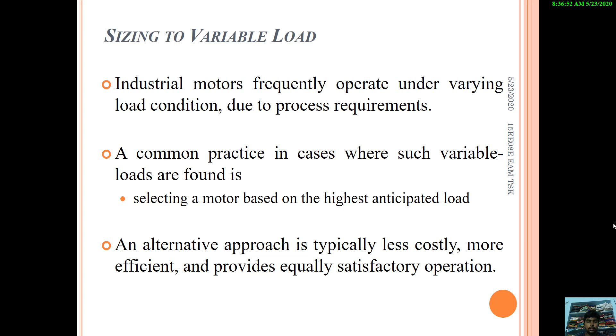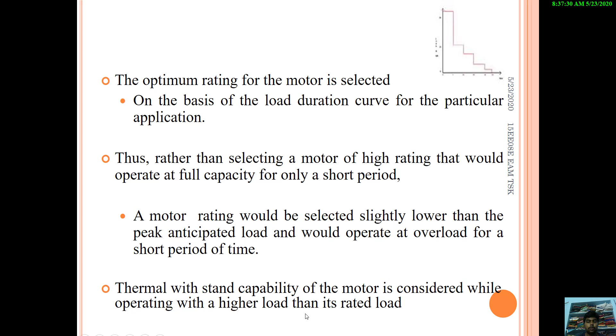An alternative approach is typically less costly, more efficient, and provides equally satisfactory operation. That is, the optimum rating for the motor is selected on the basis of the load duration curve. Based on the load duration curve, the optimum rating of the motor must be selected. The motor rating would be selected slightly lower than the peak anticipated load and would operate at overload for a short period of time. The last point is that the thermal withstand capability of the motor is considered while operating with a higher load than its rated load.